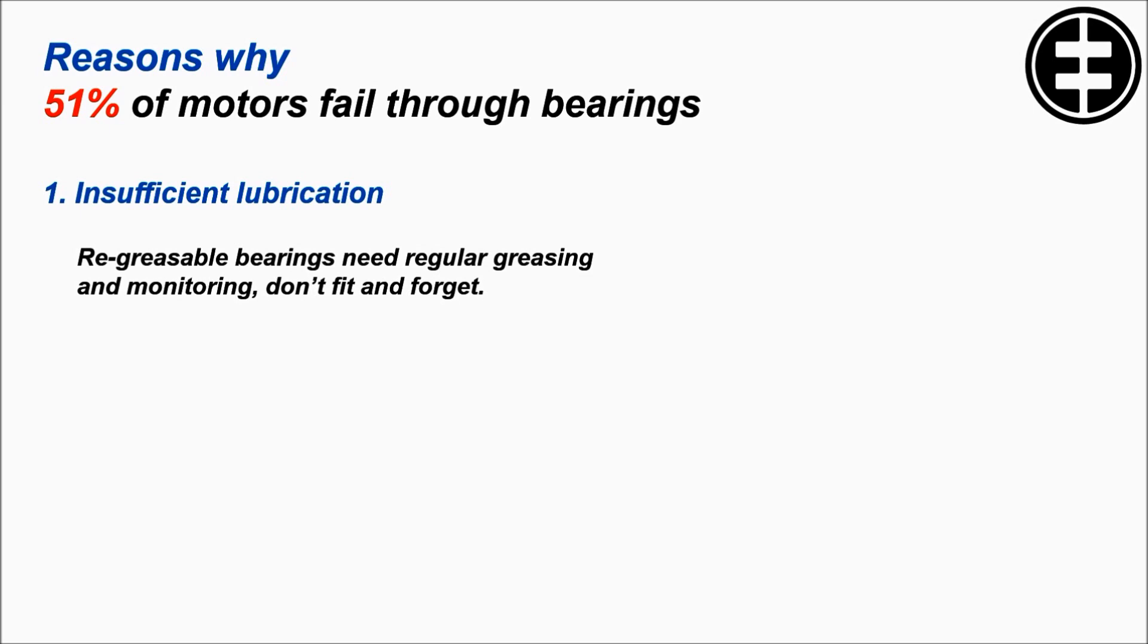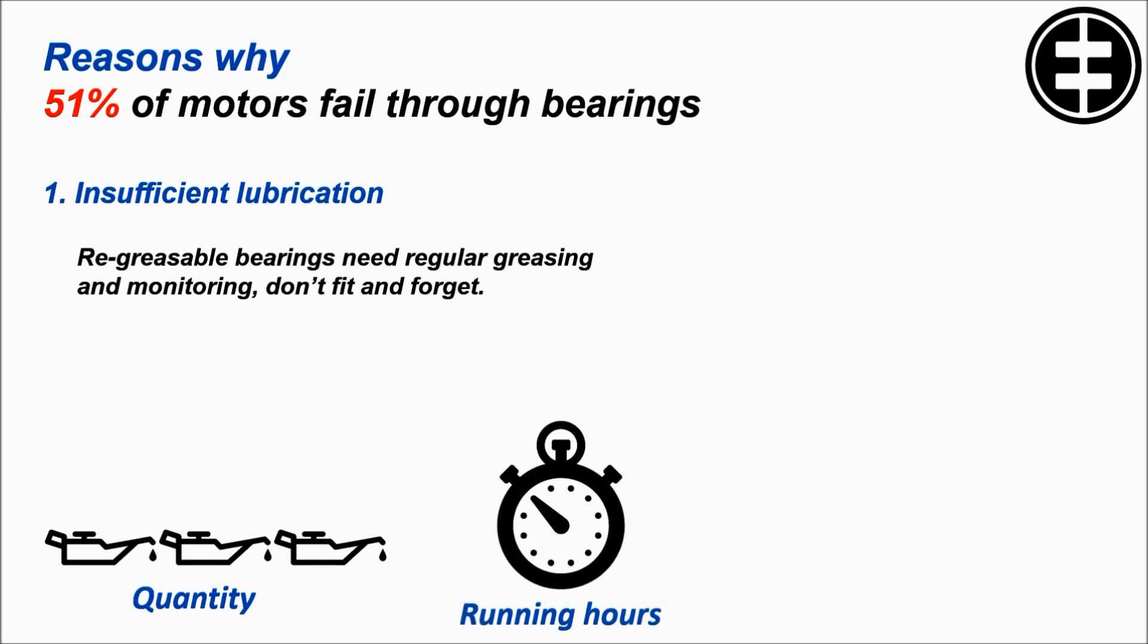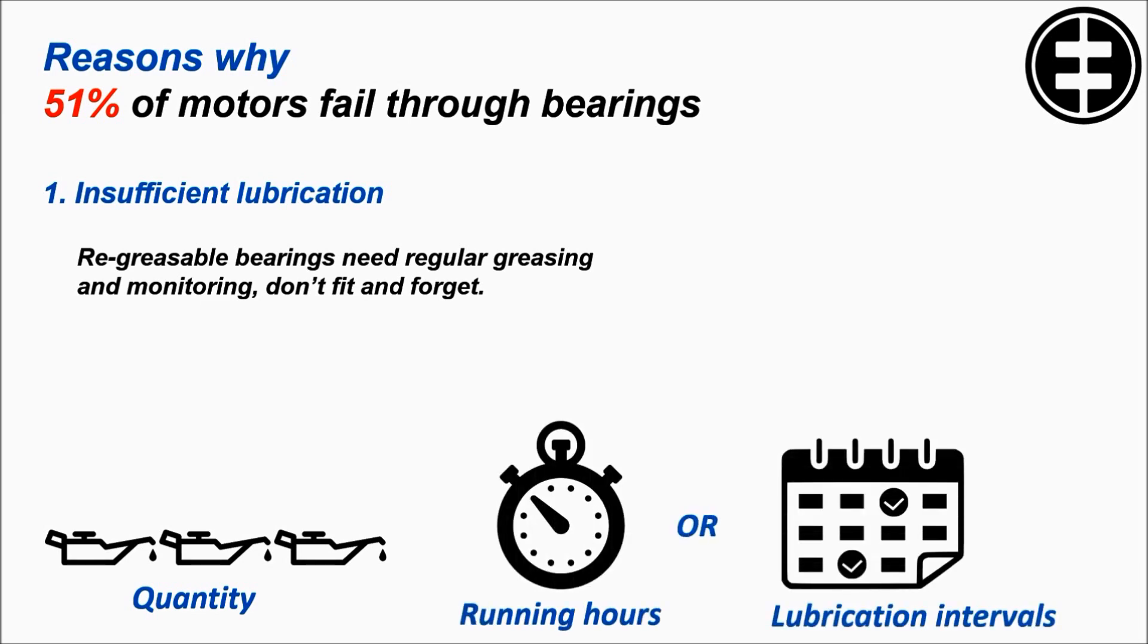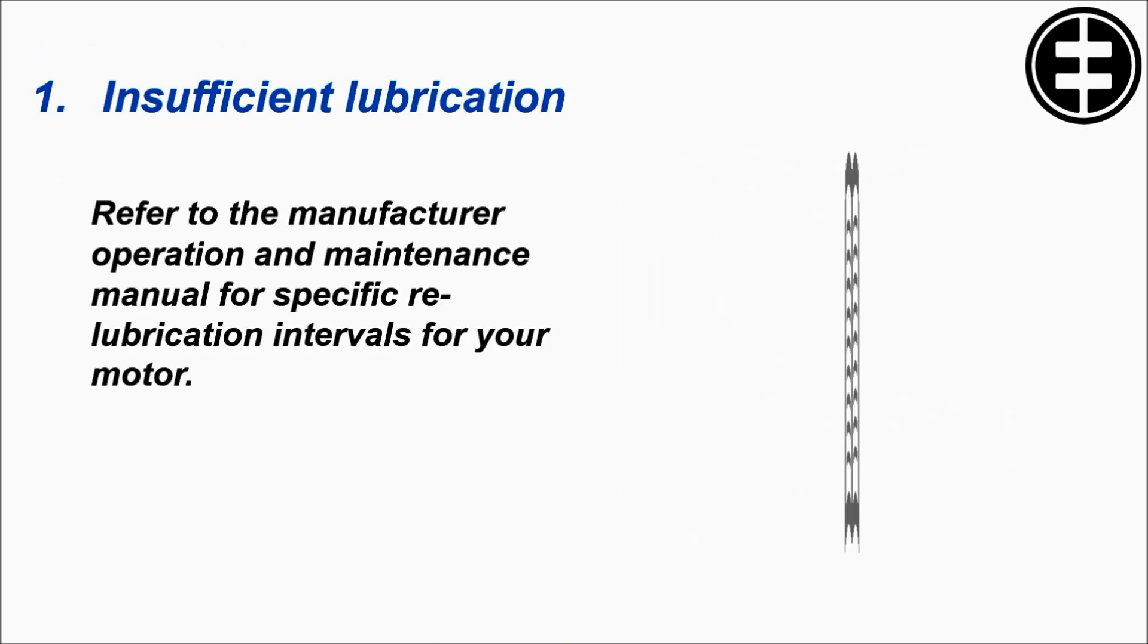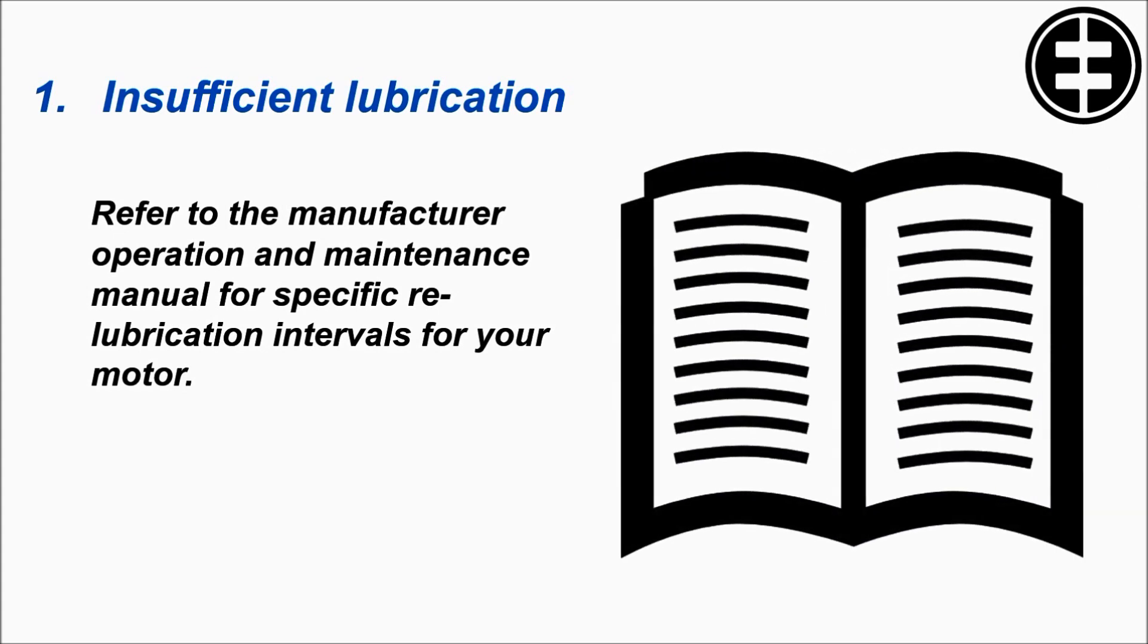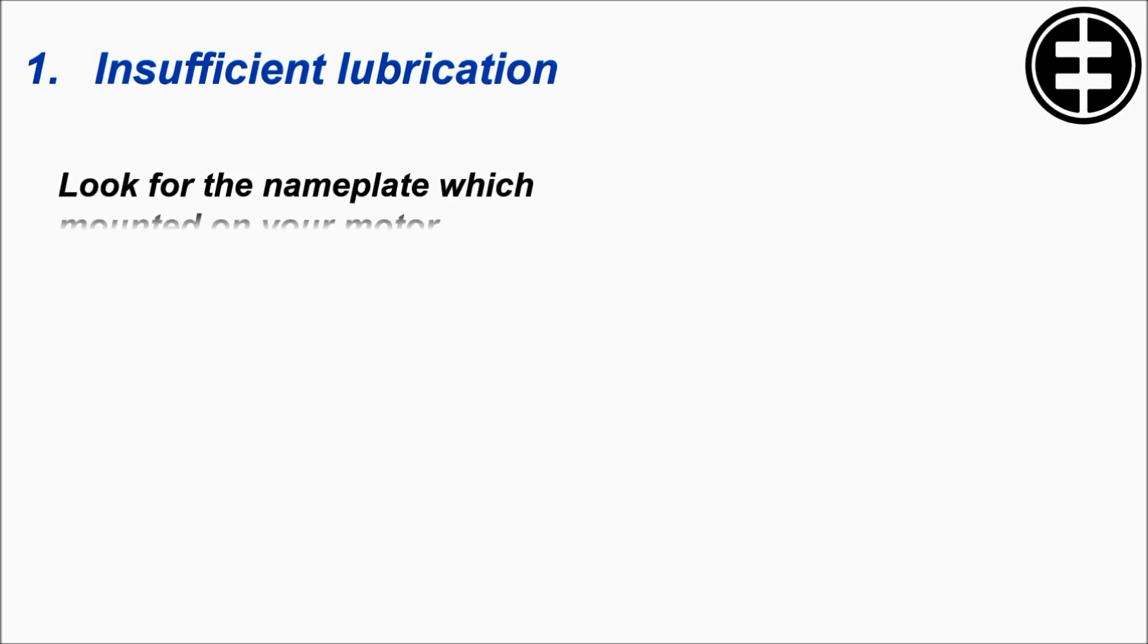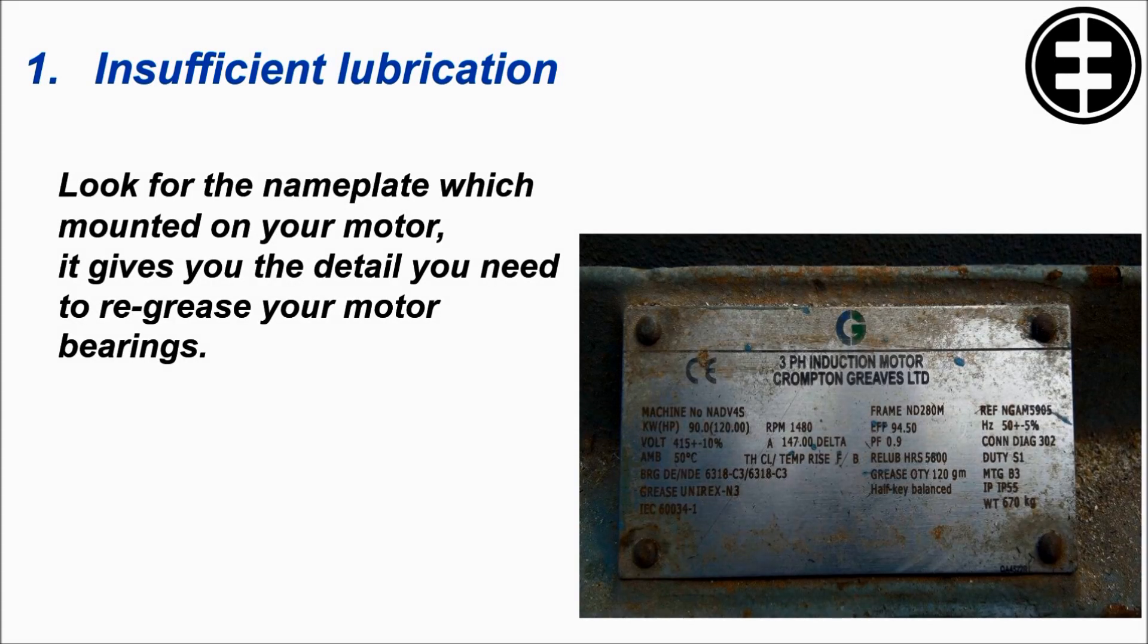Re-greasable bearings need regular greasing and monitoring. Don't fit and forget. You have to re-grease the bearing with the exact required quantity at exact operating hours or according to a greasing schedule as mentioned in the motor manual. Refer to the manufacturer's operation and maintenance manual for specific re-lubrication intervals. Look for this plate on your motor. It gives you the detail you need to re-grease your motor bearings.